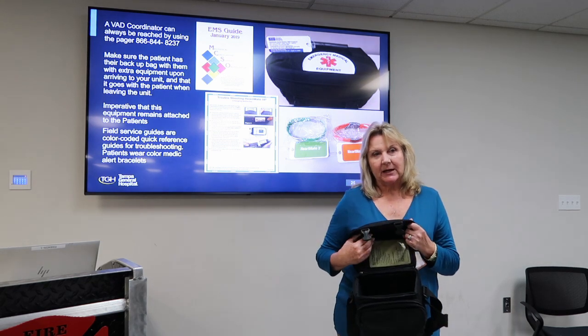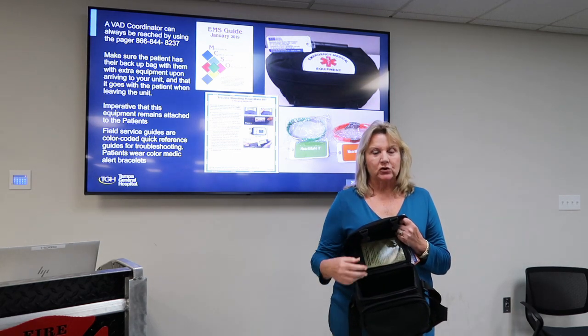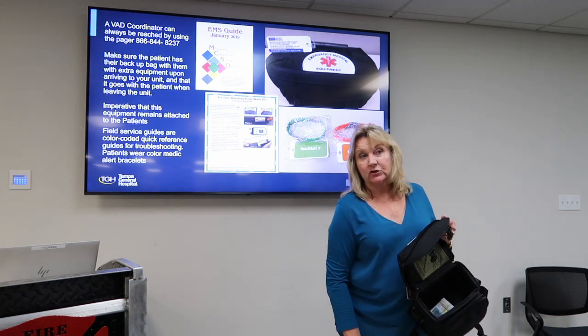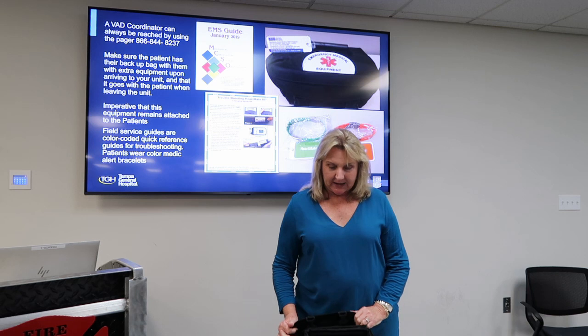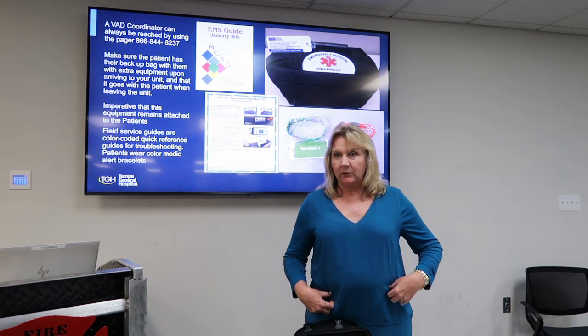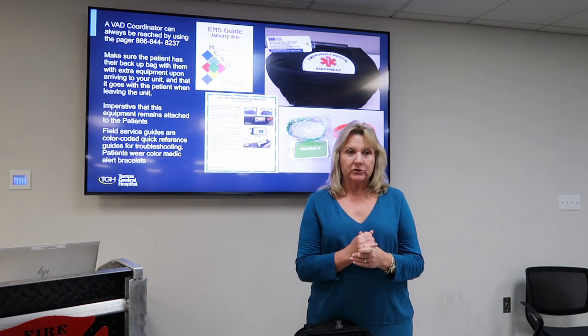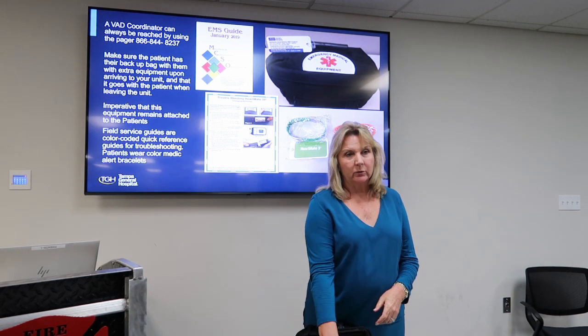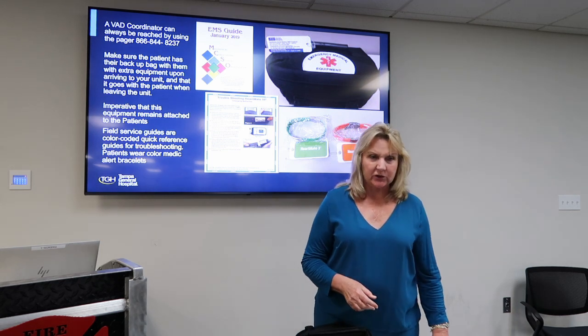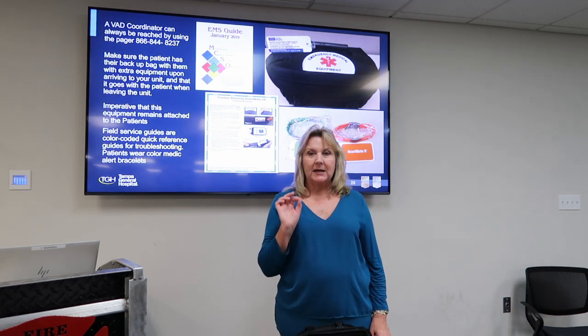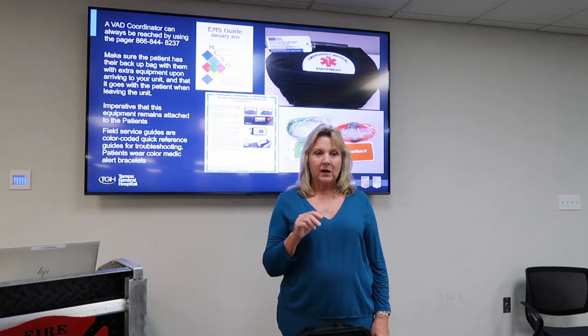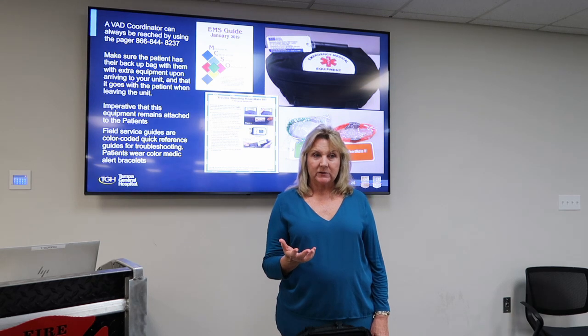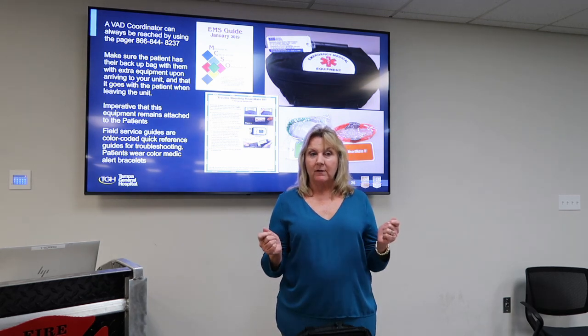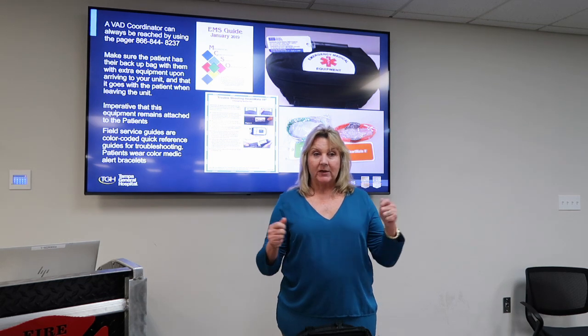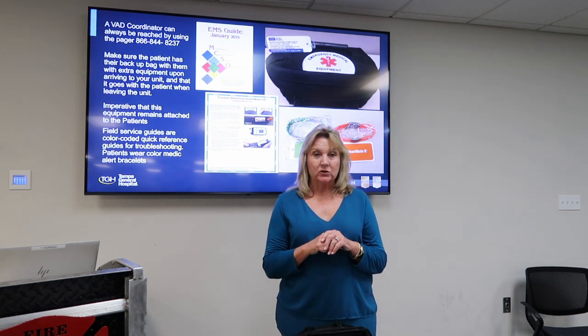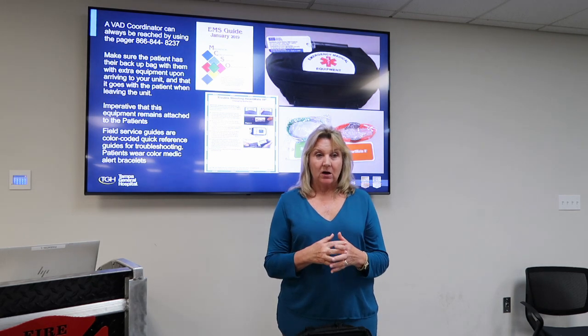Inside, patients carry their extra batteries, an extra controller, a med list, a syringe of Lovenox, so that if they're out and about and their battery alarm goes off, they can quickly change and replenish with two fresh batteries. The controller would be only for emergency situations. We do teach patients how to change their controller, but we do not advise them to do that alone. They need to be with somebody, because when you take a controller off, the device stops, and if they can't make those connections to reestablish the controller, the device stays off.